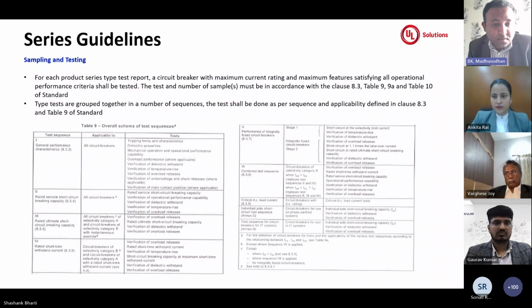Whereas the other sequences, from sequence 2 to sequence 6, speak about the short circuit test that is going to happen on the breaker, followed by all the post tests for the products. So there are various sequences that have been given in the standard. Based on the declaration on the product, some of the sequences will not be applicable, because that is based on the category you declare for the products. So, whether it is category A or B.